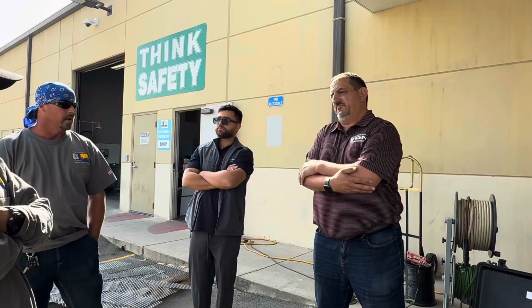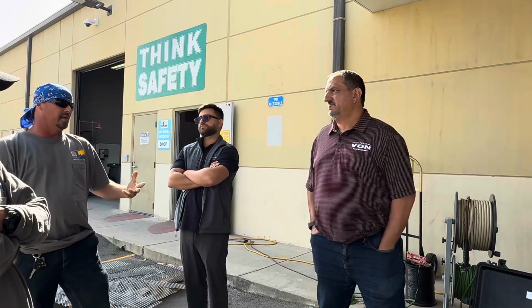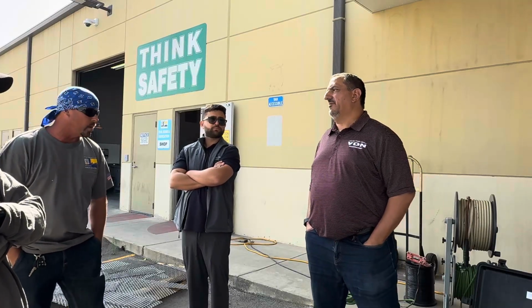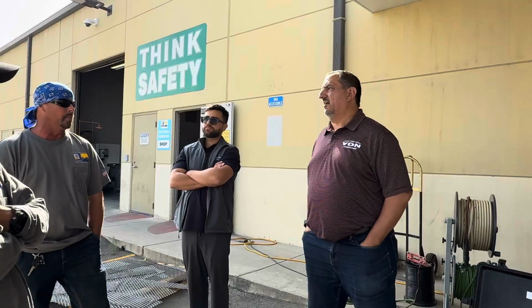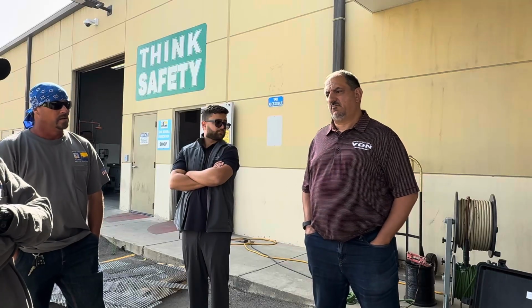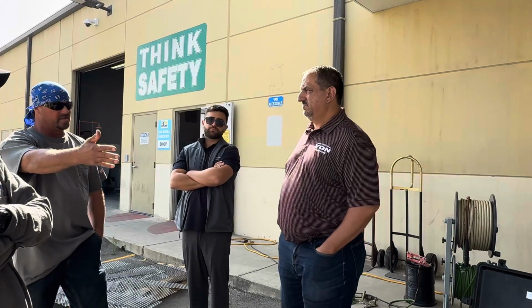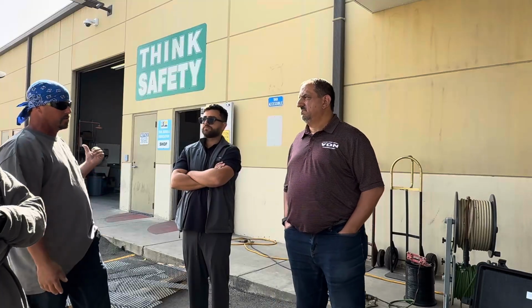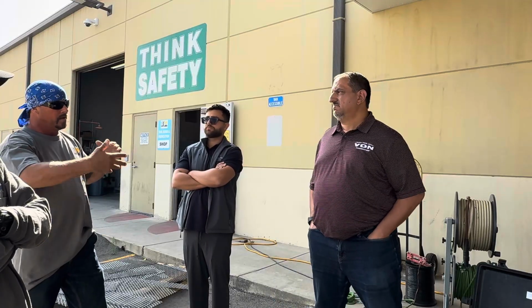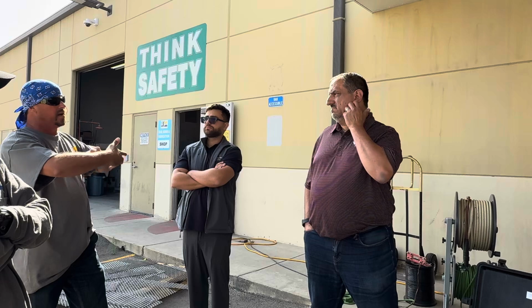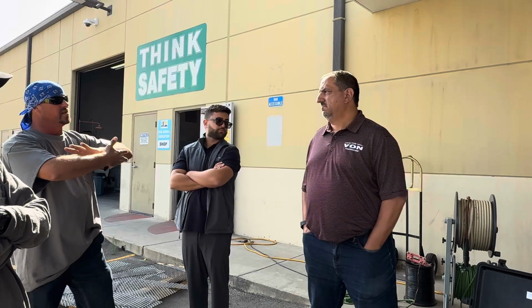Exactly, and to me, if the concentric's bad, you probably ought to replace the cable anyway because it's not operating right. So if you've got a good system on one side, jumper the neutral, and on the other side with the compressor, set it up the same way—if it's both concentrics out, it's gonna act the same.